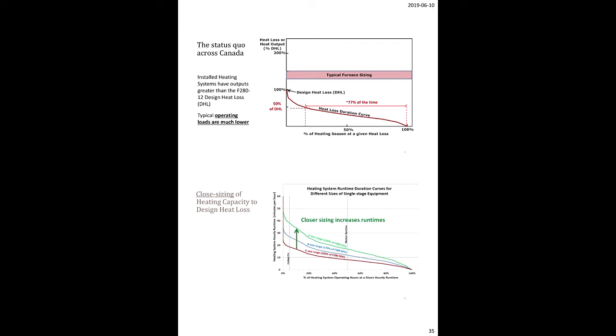The reason moisture levels were going up and basements turned into swamps was that the air conditioning was short cycling, coming on and shutting right off. The air conditioner doesn't start removing moisture until it's run for 8.5 minutes. If it short cycles, it cools the air but doesn't dry it, so you get a swamp.